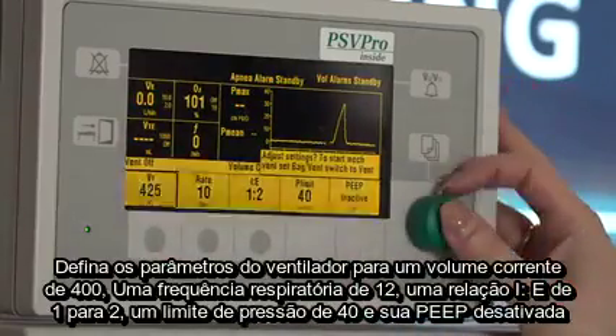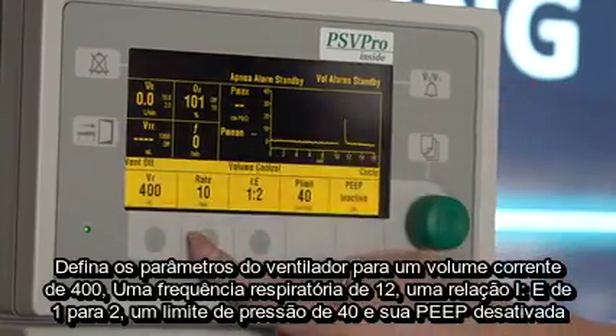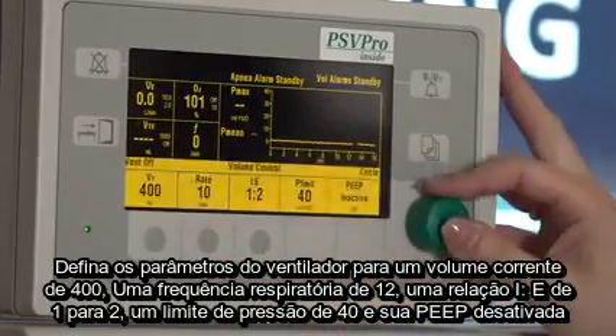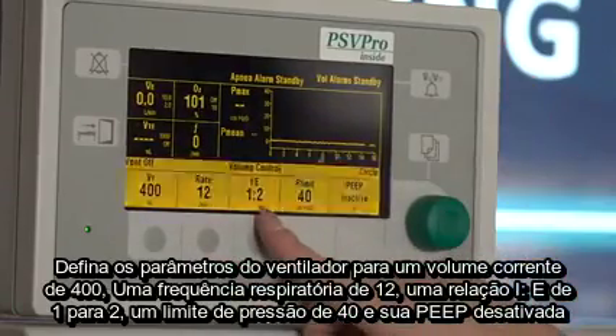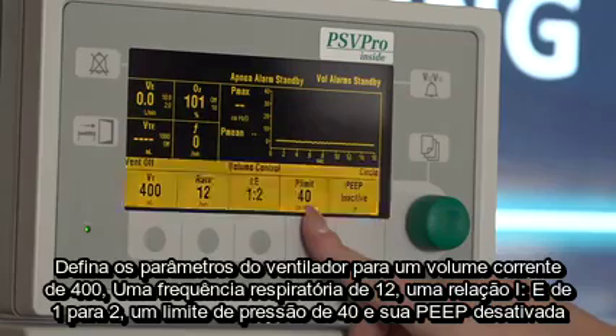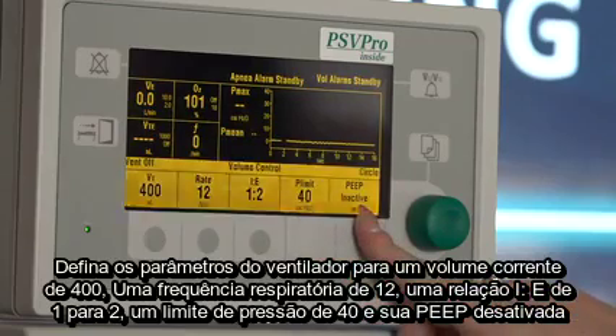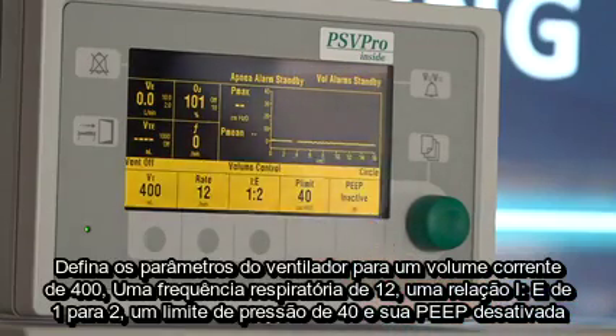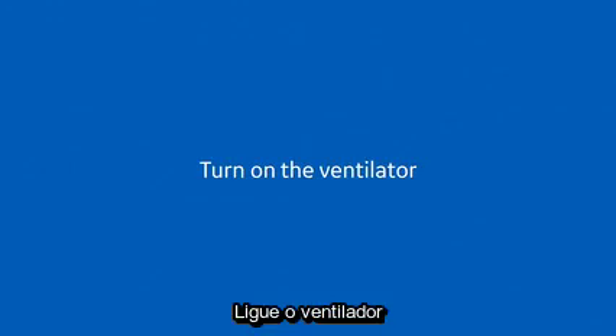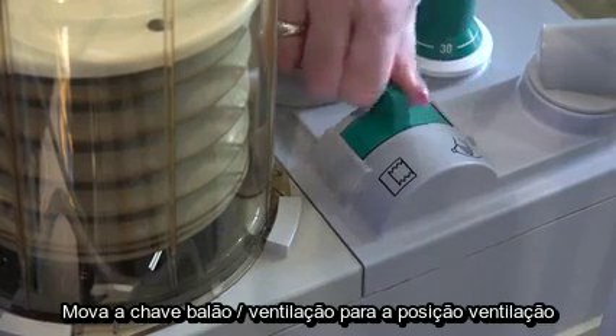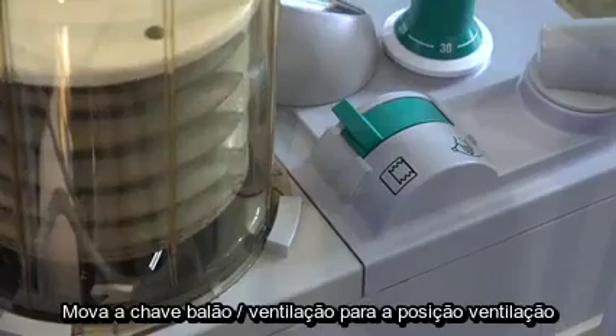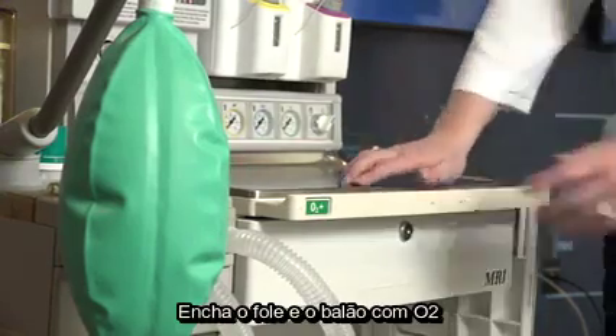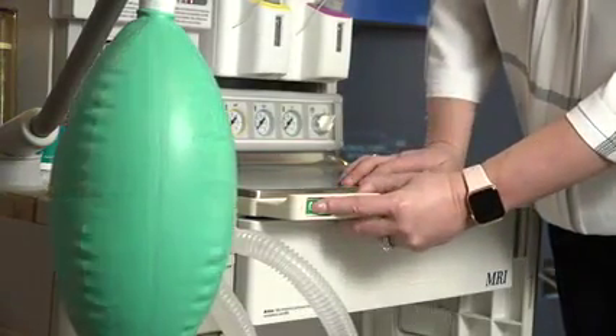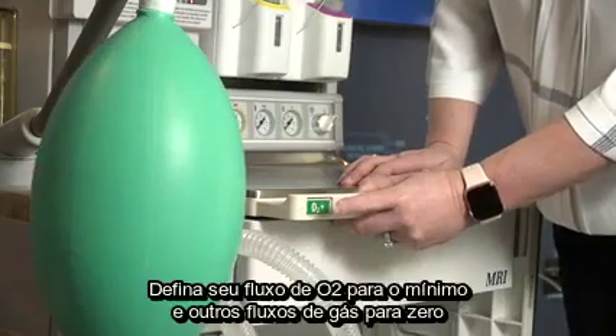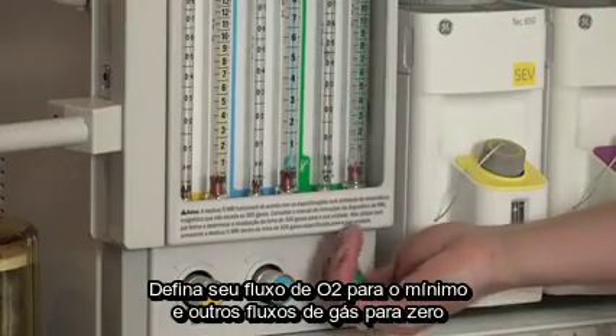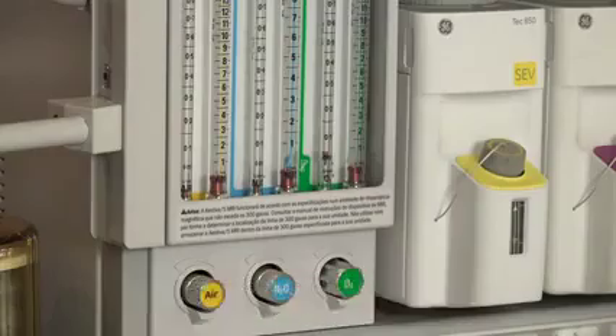Set ventilator parameters to a tidal volume of 400, a respiratory rate of 12, an I:E ratio of 1:2, a pressure limit of 40, and your PEEP to off. Turn on the ventilator. Move the bag to vent switch to the vent position. Fill the bellows and the breathing bag with O2. Set your O2 flow to minimum and other gas flows to 0.